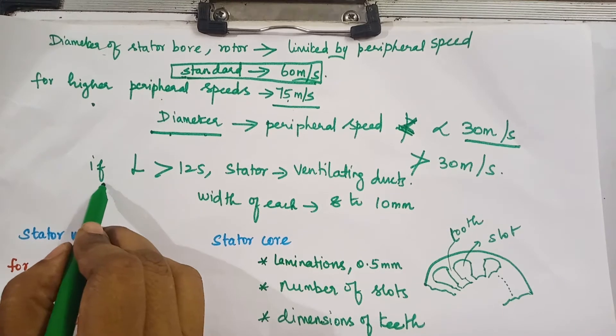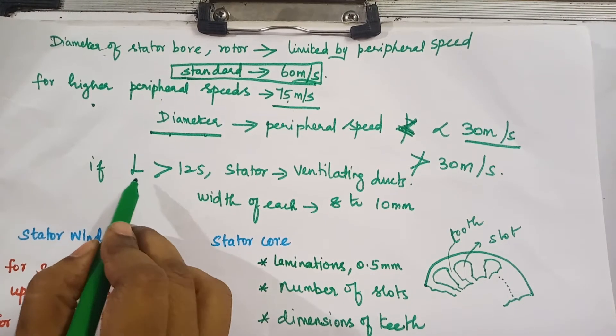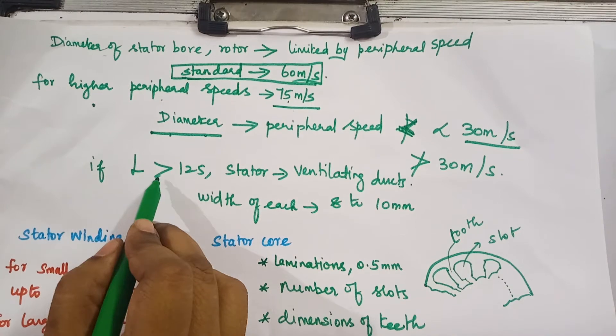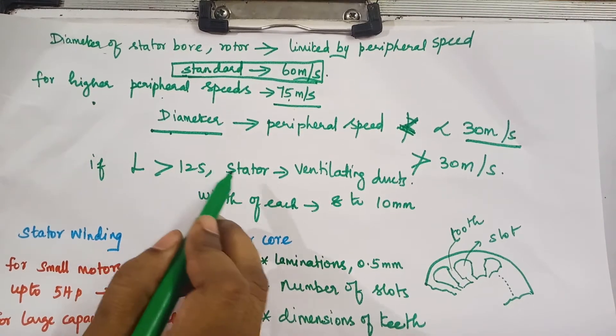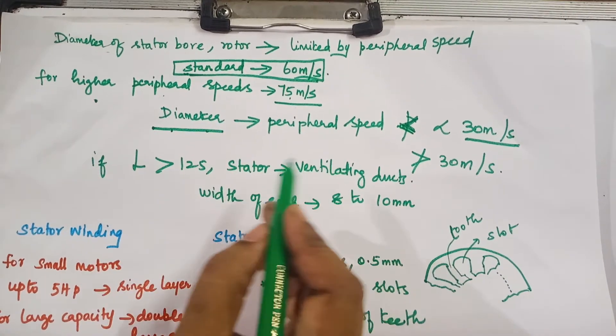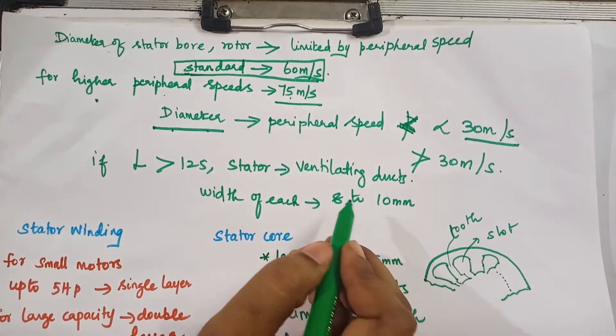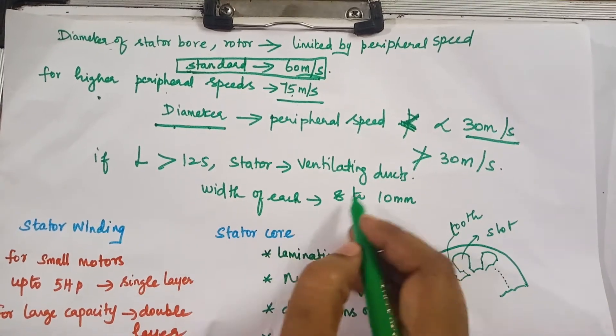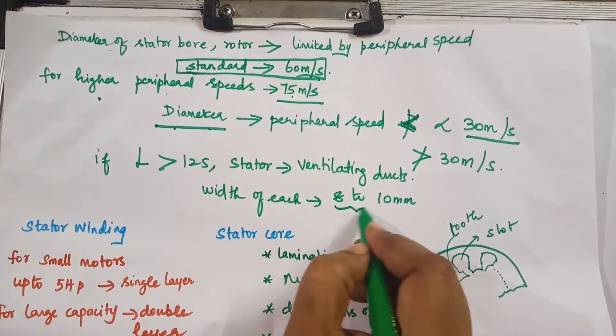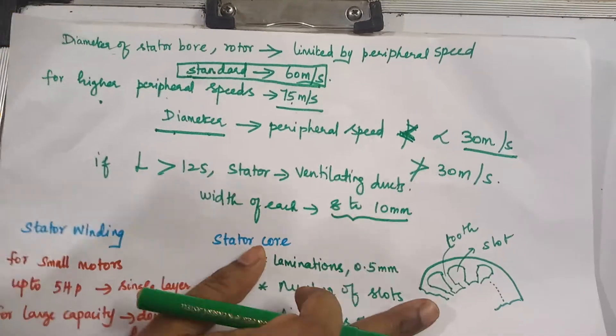If the length of the stator is greater than 125 mm, you have to use ventilation ducts. The width of the ventilation ducts varies between 8 to 10 mm.